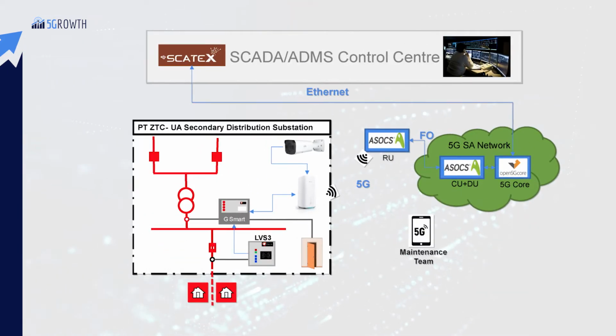In the first use case, the operator in the control center gets real-time information concerning a fault occurring inside the secondary substation, including live telemetry of the electrical equipment and video streaming from the substation interior. This way supporting a faster and more accurate maintenance planning with a better evaluation of the human and physical needs to resolve the fault and restore the power supply, therefore reducing the utility OPEX.